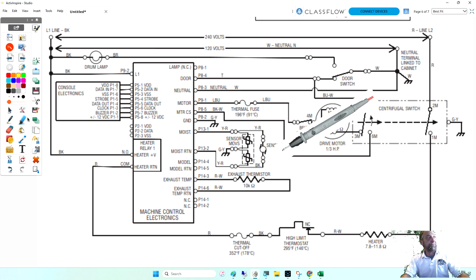When doing a voltage test, if the component's good, voltage will be on both sides of it. Like if you're testing a heating element on a dryer: no voltage, no voltage, no voltage, then voltage, voltage. If I have 240 on this terminal and this terminal, that means power is coming in and made it this far. When I get here and have 0, it's because this black wire's broken and not giving power to that point.